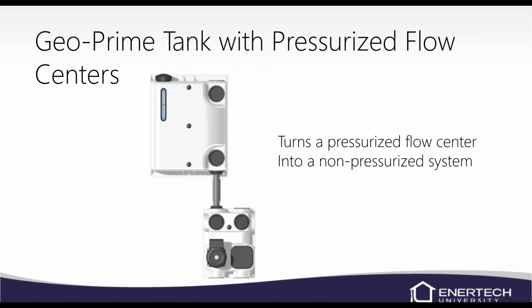A Geo-Prime, basically, turns a pressurized flow center into a non-pressurized flow center. So now this Geo-Prime tank is like your non-pressurized standing column of water. This will give your pump pressure so they don't cavitate. It's basically just a reservoir with a holding tank. Again, it's got a little gas cap, so it will bleed air out as air comes into this tank. And again, it's got a sight glass. The homeowner can fill it up when it gets low. Real simple way to turn it into a non-pressurized system when you've got issues with a little bit of air in the system.